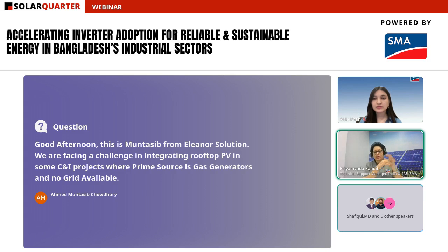So depending on the type of generators and how they're controlled, we can definitely work with that. These gas generators typically have controllers, and we have a controller we used to call the PV diesel hybrid controller. Now we just call it the hybrid controller, because with it we're also able to integrate multiple sources. So we can have solar plus a gas or diesel generator plus batteries plus wind, integrating all of them into a single energy management system.